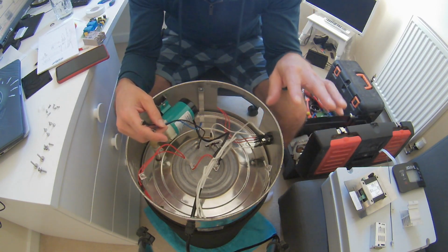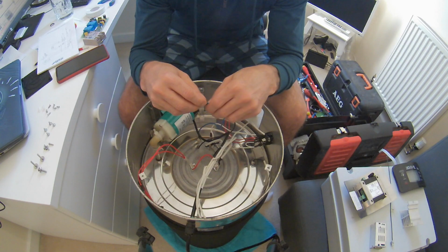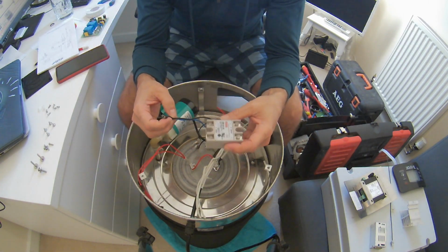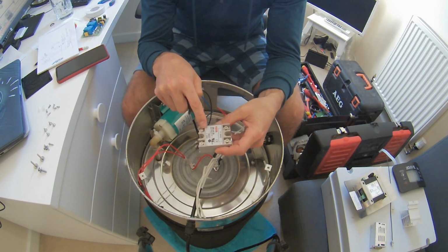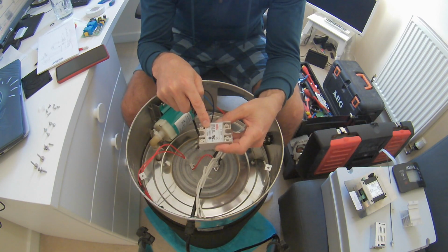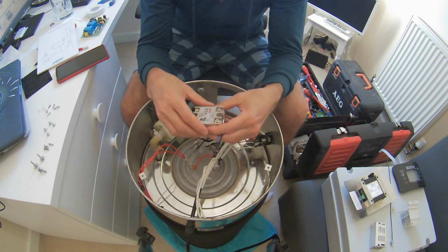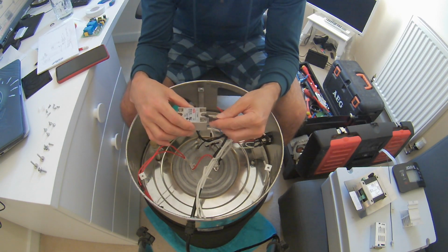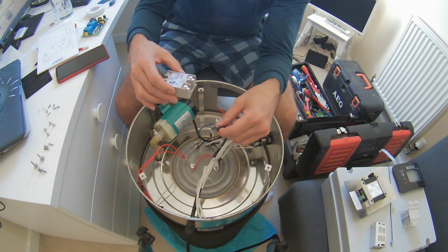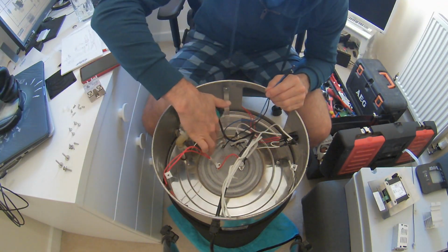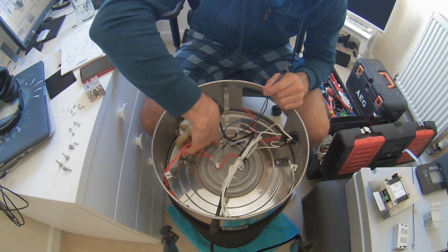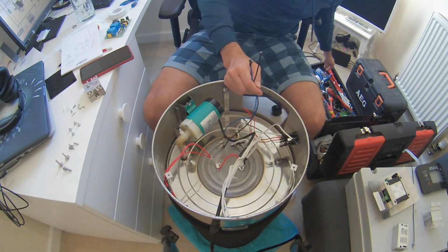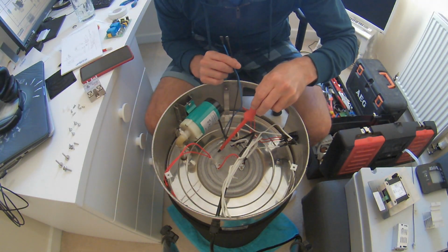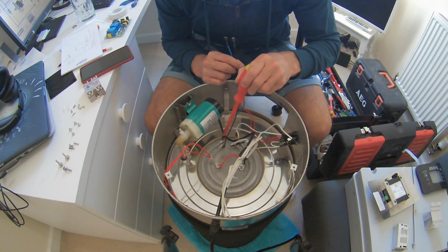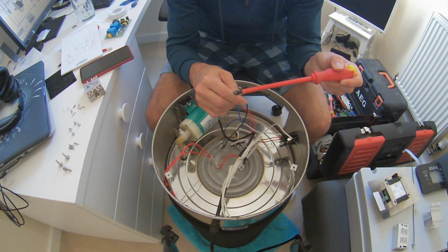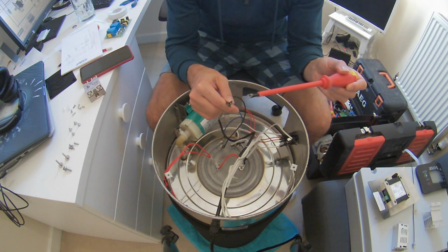Okay, what we need to do first is connect up the solid state relay. So this is the solid state relay, we've got numbered 1, 2, 3 and 4. 1 and 2 are high voltage, 3 and 4 are 12 volt or low voltage. So these 2 will get cut and both go into number 2. We'll do that quickly. Just to be sure, you see it's the 2 that are coming off either end of this - I'll point with a screwdriver. The 2 cables that are coming off either end of the heating elements themselves. So this will be for both heating elements, and it'll go into port 2 on the SSR.